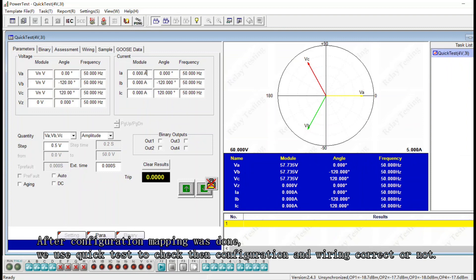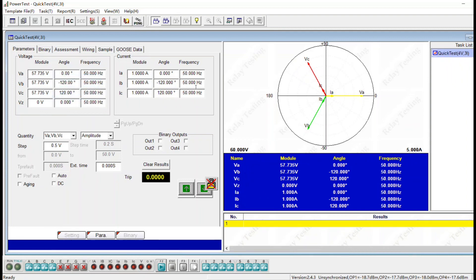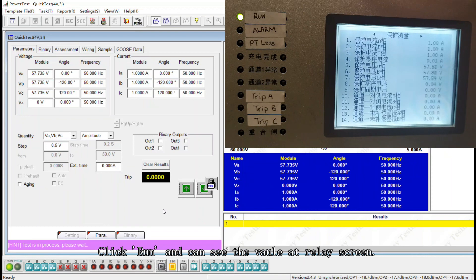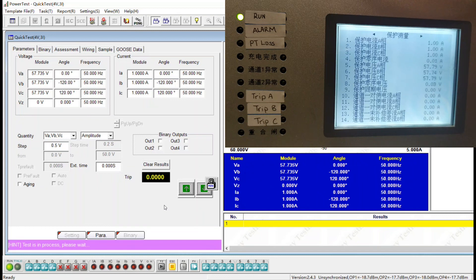After the Goose mapping is done, we use the quick test module to confirm the signal quality using 1 ampere and nominal voltage, and quick run. You should be able to see the values on the relay screen. As we can see, all the signals are correct.